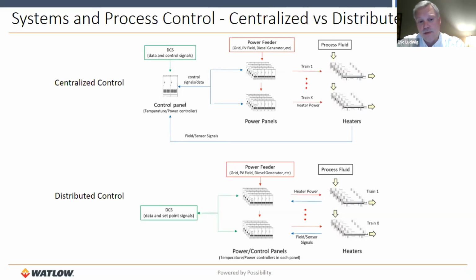In the bottom system, we have more of a distributed control system where the DCS talks to all of the power panels, and the power and the controls are kind of combined together within those power panels. In that particular system, your DCS is talking to almost each one of the power panels independently. This has some benefits to it with regards to reliability of the network. In your centralized control system above, everything goes through a single control panel. If something were to fail in that control panel, you likely lose your entire heater field. In a distributed control system, if one of the communications or one of the circuits, so to say, goes out, then it's just that circuit that goes out. We still have control of the other circuits in the system. So again, there's positives and benefits to each one of these that need to be understood.